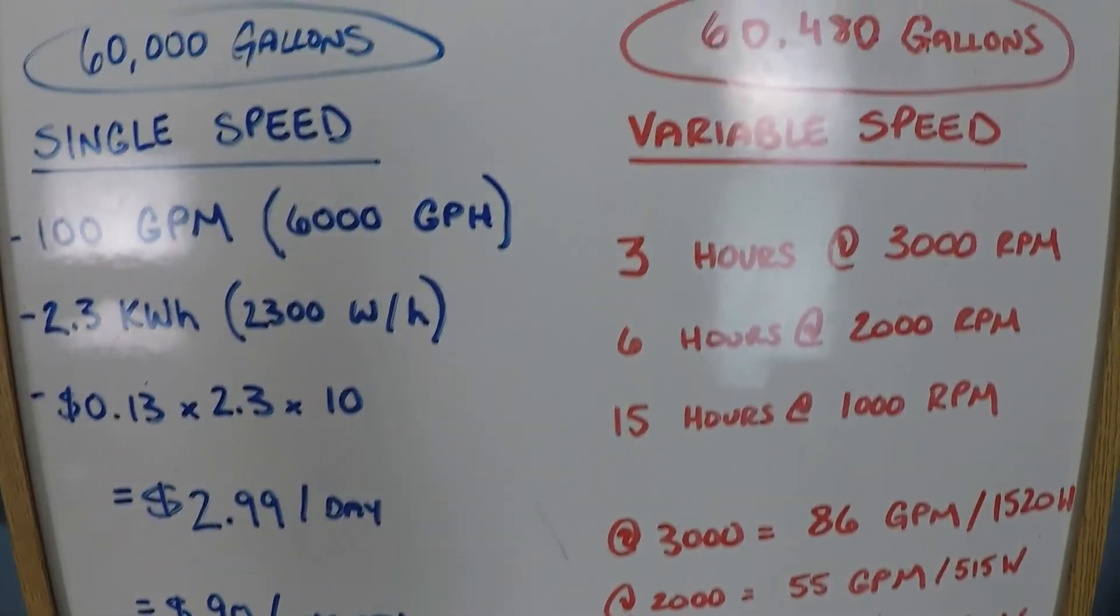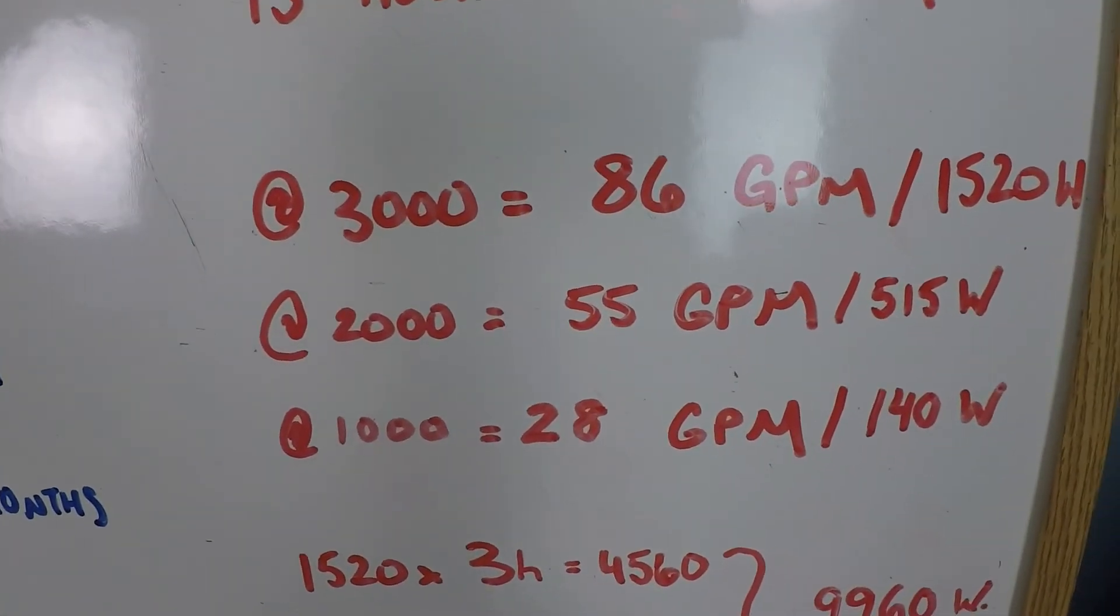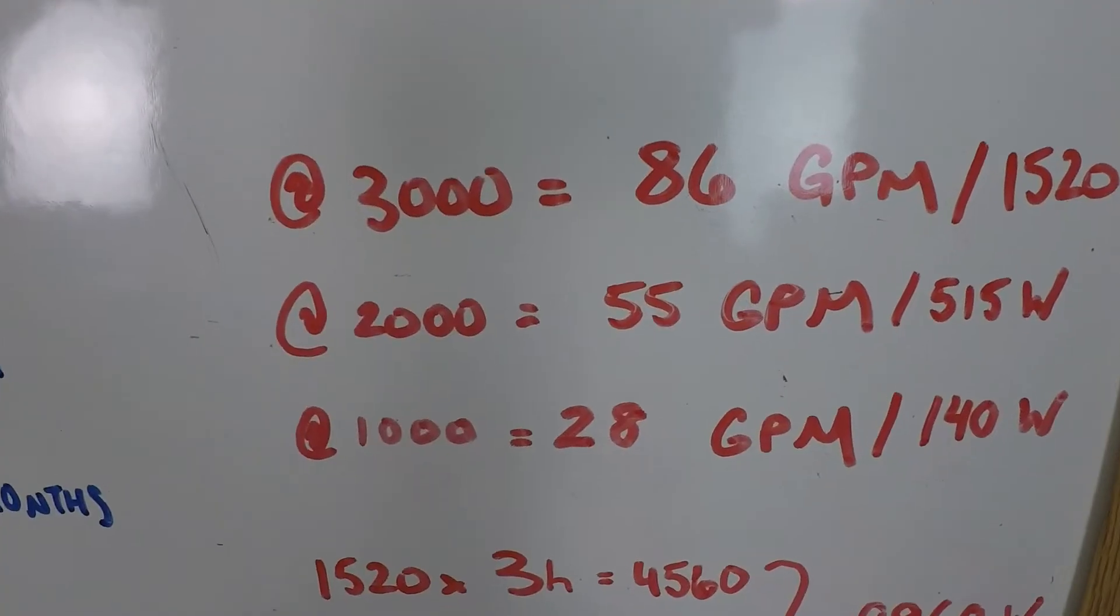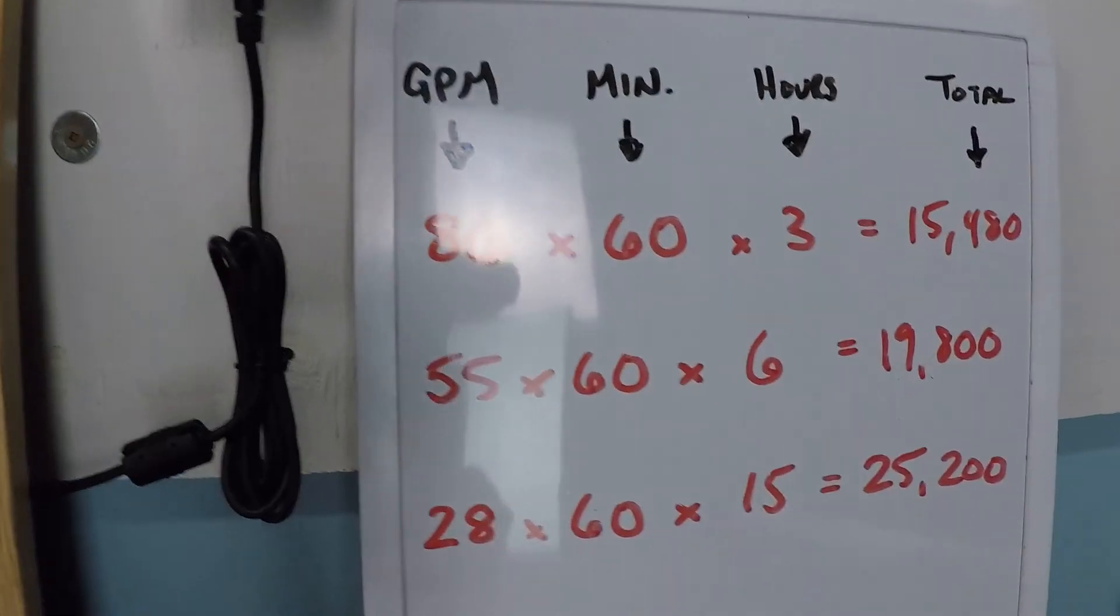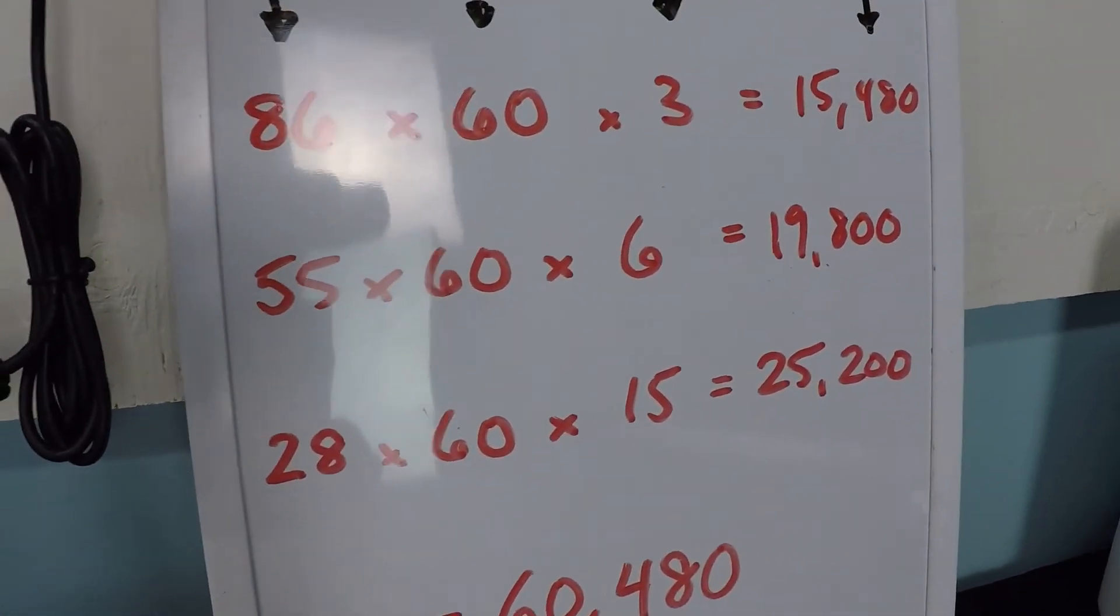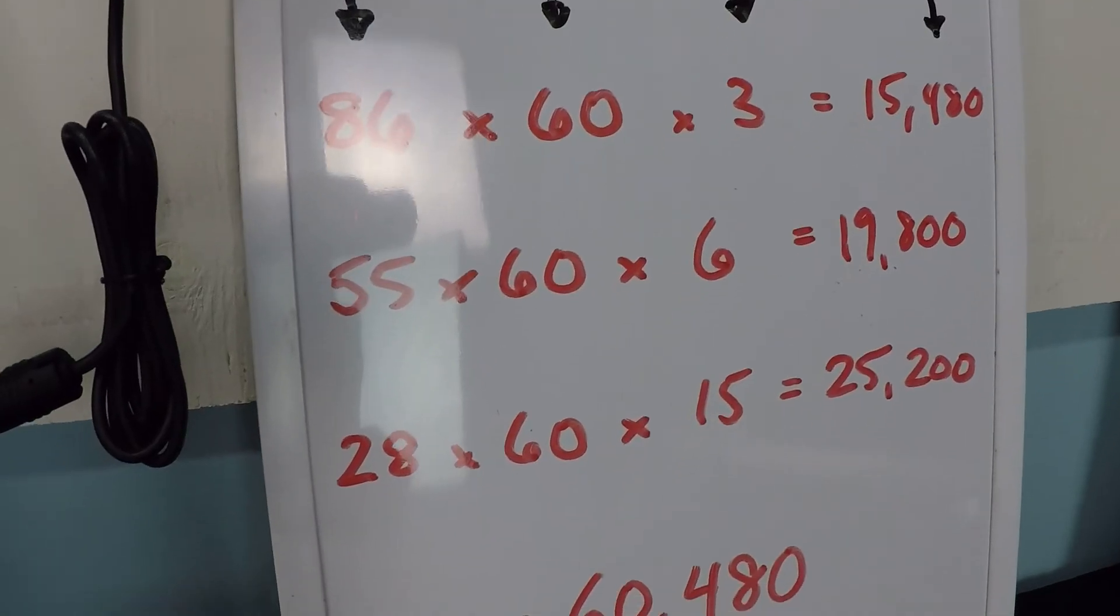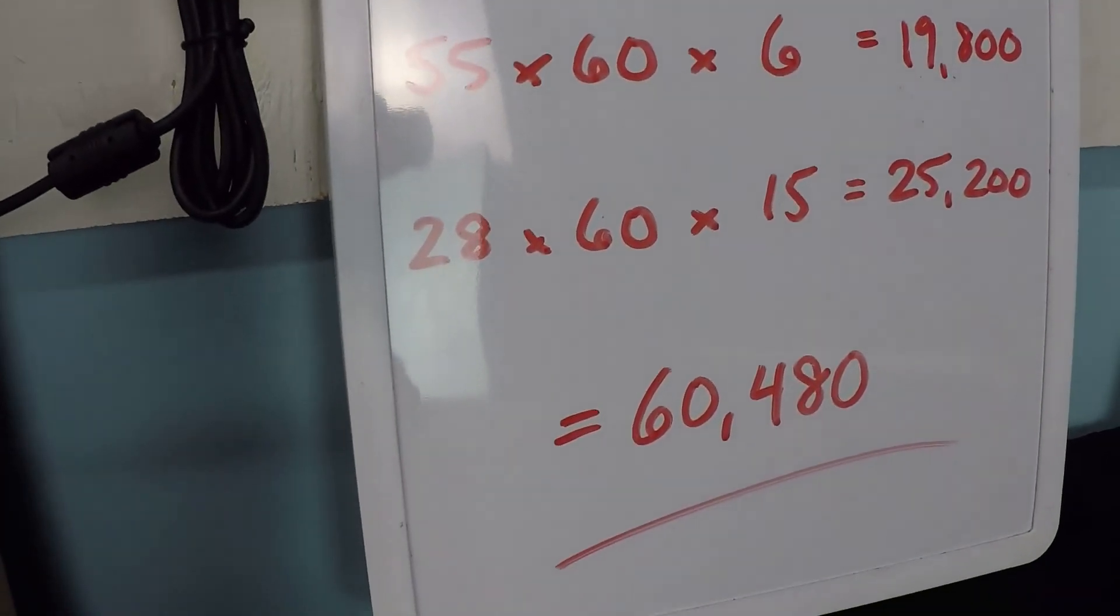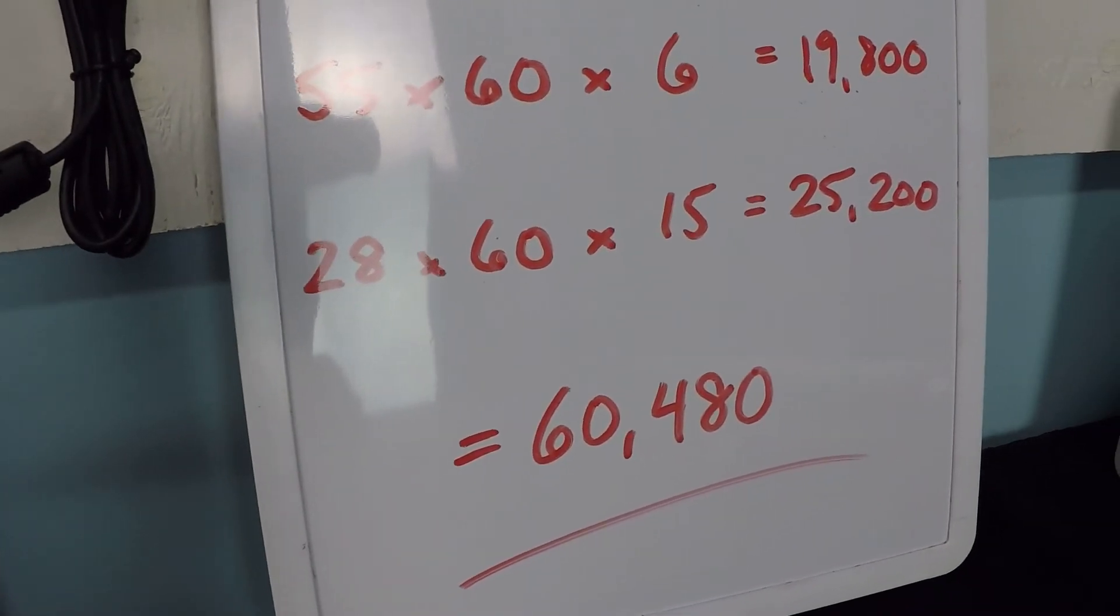And because you might be interested in seeing the calculations behind this, what are we getting here? For three hours, we had 86 gallons per minute, and then for six hours, we had 55, and then for 15 hours, we had 28. So here are those numbers here as well. In the three-hour high-speed schedule, we got 15,000 gallons, whereas in the 15 hours at low speed, you got 25,000 gallons.